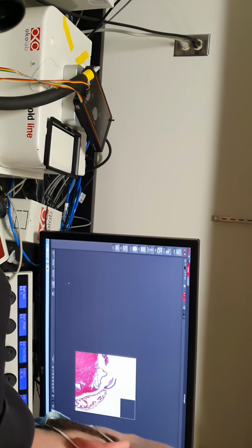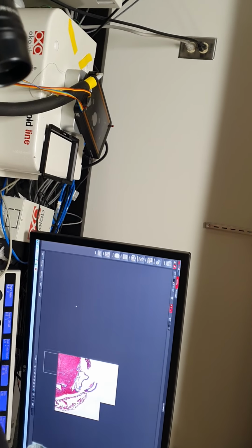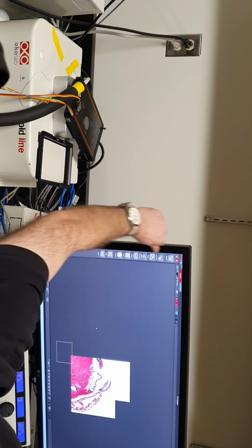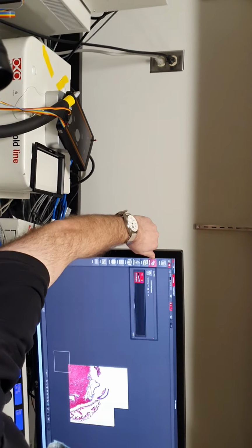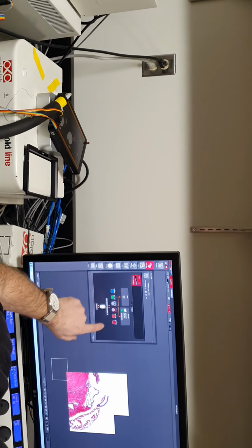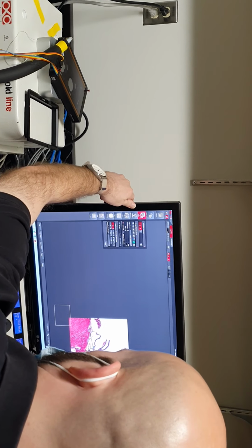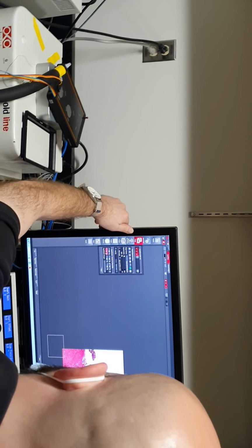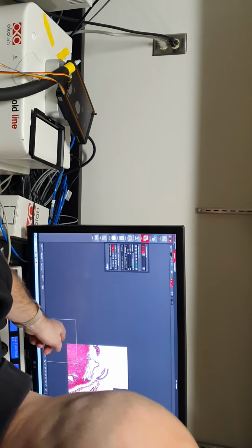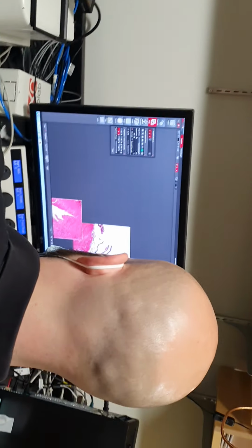And we could either do that with this objective that we're planning on using, or to make it quicker, what we can do is switch to a lower magnification objective. We still have all the same image controls, but they're now in these tabs on the left. So you can see here, this is where we set up our channels. Here's where we have all of our sort of camera parameters. And so we could say switch to the 5x objective. And so now we can see our field of view is substantially larger. Click live, and then we hit spiral again.